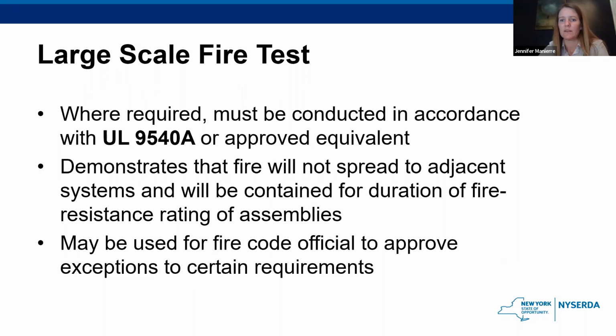On top of that, the larger systems need to undergo large-scale fire testing. And UL 9540A is basically a testing protocol, and it would be done by an approved testing laboratory. But essentially what they do is take a representative energy storage system, the one that someone is proposing to install, and they try to force it into thermal runaway and try to induce a fire. And it's sort of a multi-step process. So if they force a cell into thermal runaway and nothing happens, cool, great. This is a very safe system. Most of the time, if you're going to force it into thermal runaway, you probably are going to create a fire. So they're forcing the systems to catch fire and then basically seeing what happens.